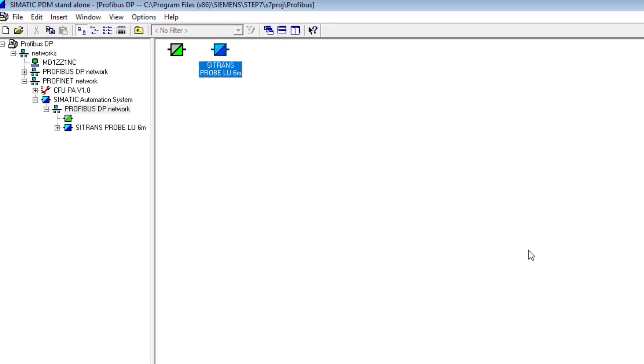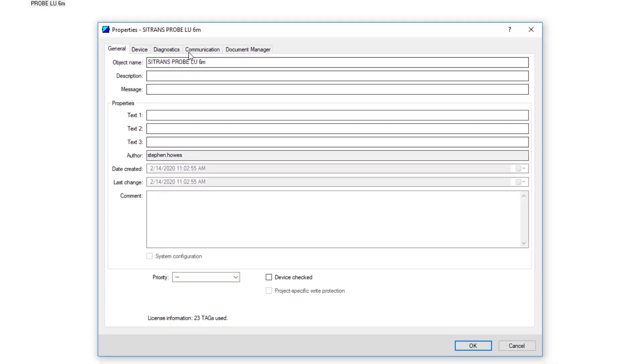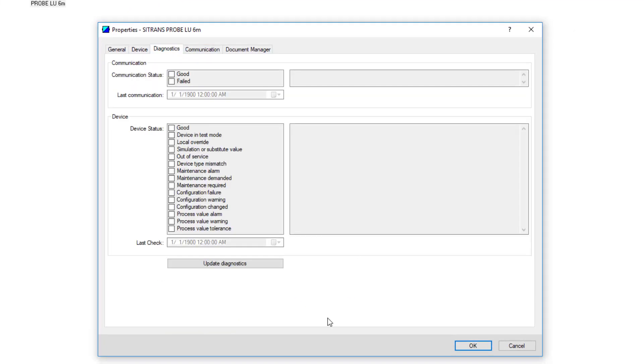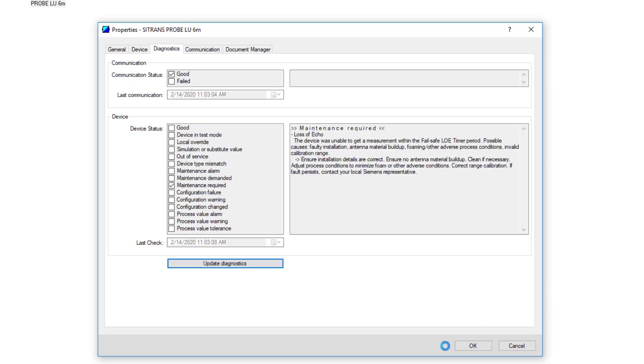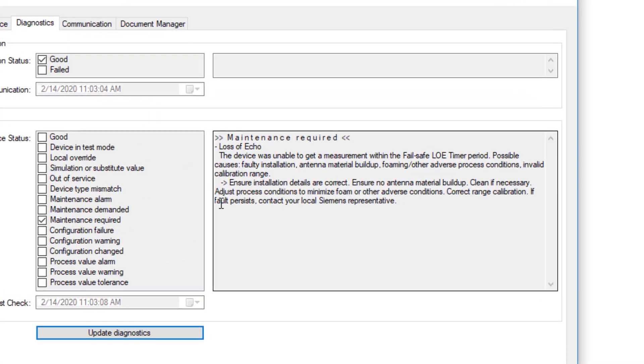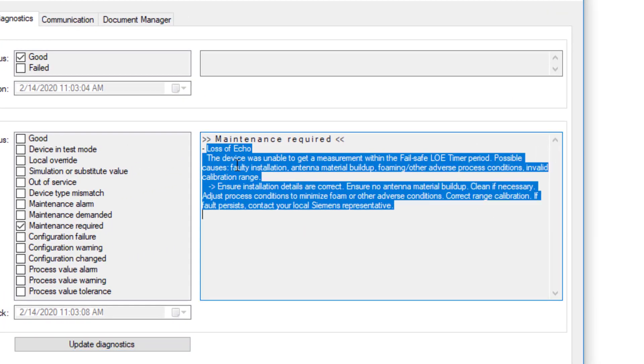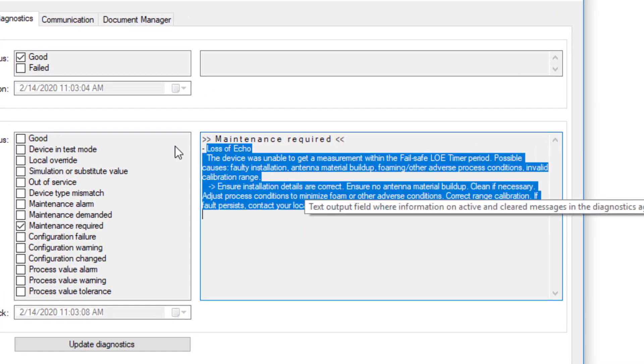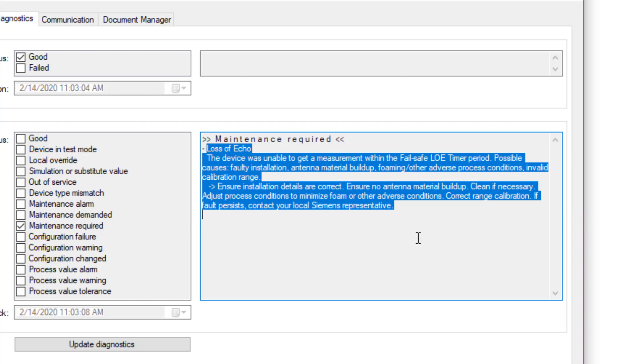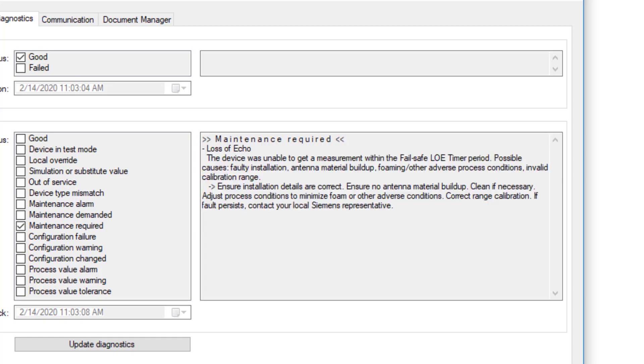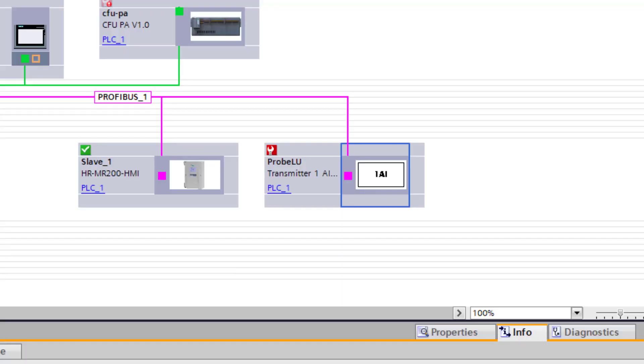If I want to see what's wrong with it, I can go to object properties, diagnostics, and I'll take my diagnostics. So I've got loss of echo, it's gone to a failsafe level. See clearly there from PDM what's wrong with my device. This is why the two software packages really work in tandem. TIA portal tells me I've got an error, PDM tells me what the error is, but it also tells me how to fix it.